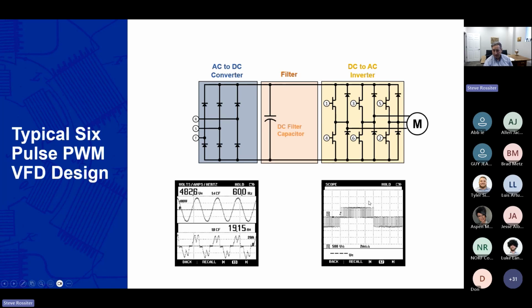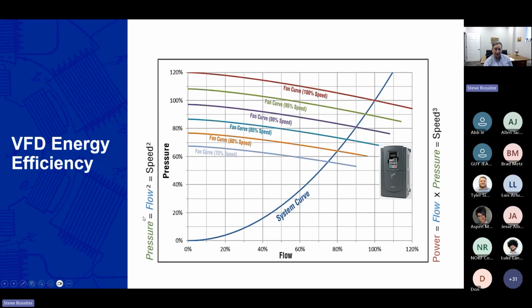So kind of like you see in this right bottom graph, if you take a number of very small pulses and longer pulses, that would look to the motor similar to what a waveform would look like. And so, while not perfect, the motor can tolerate it. While not perfect on the input, it generally in all of the 70s and 80s grew and grew and grew in popularity. And the primary reason for this is because of something we call the affinity laws, which is a huge motivator in applications for flow loads that can reduce energy consumption.